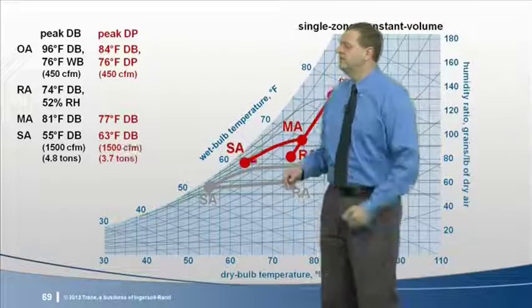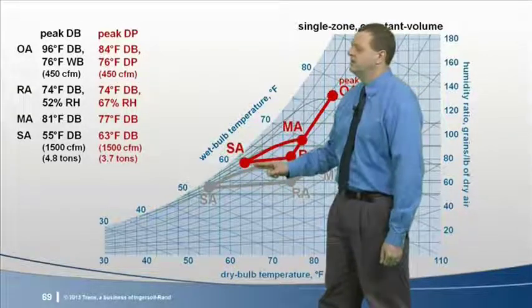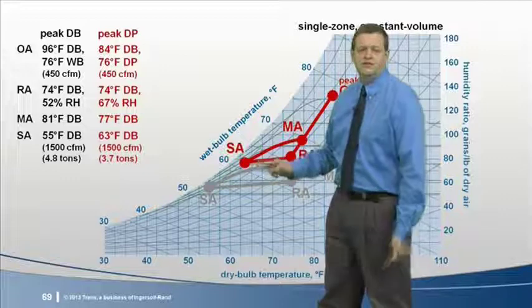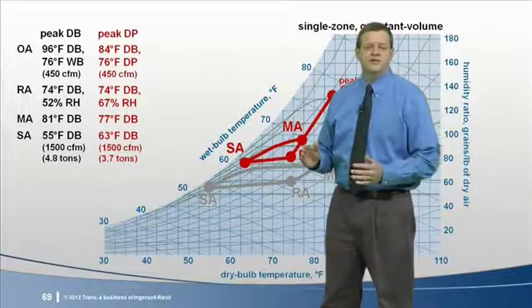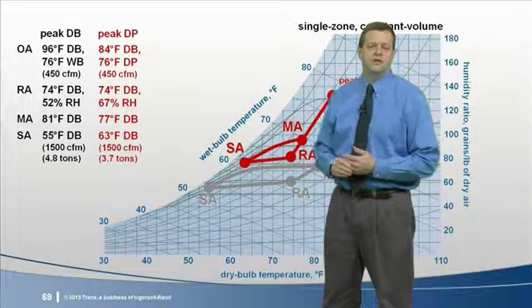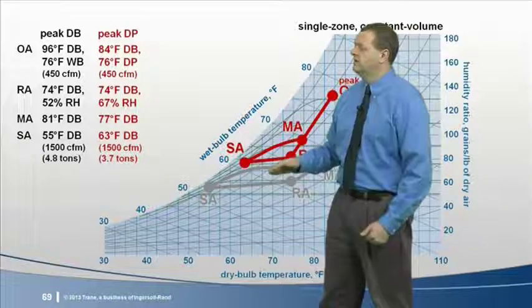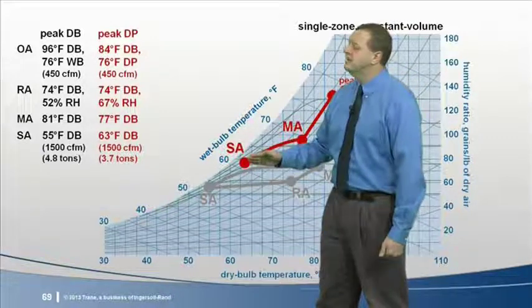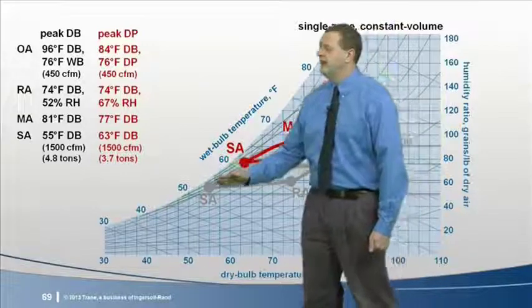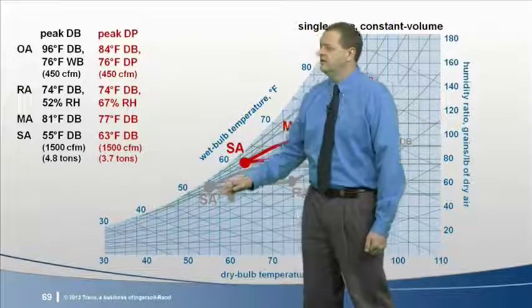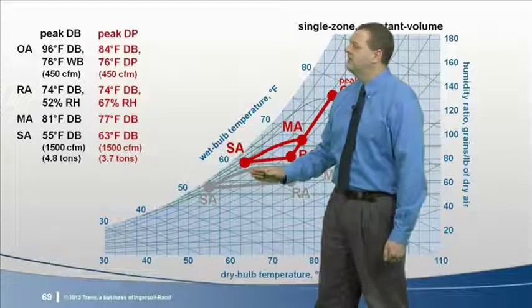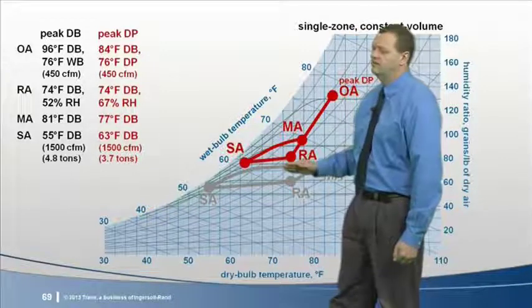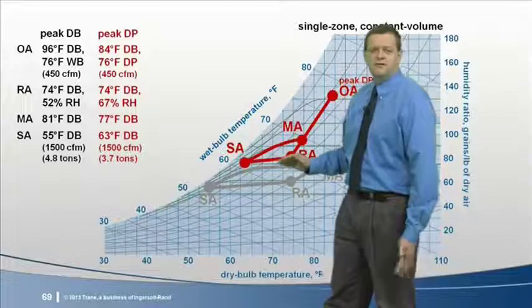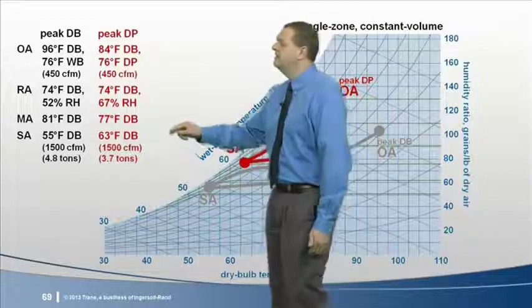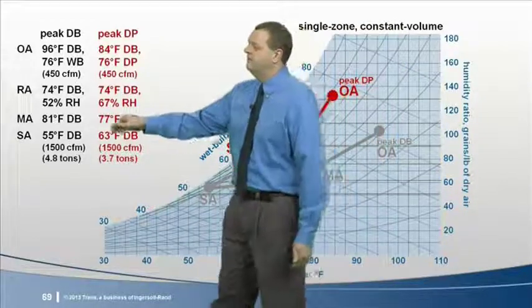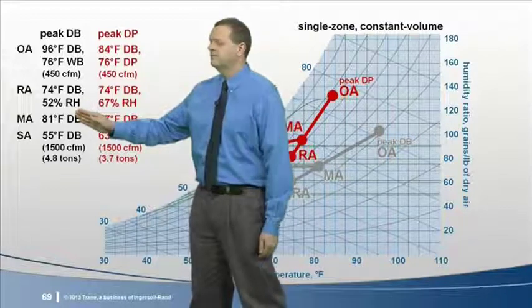Now, although delivering this warmer air prevents overcooling and maintains the zone temperature at set point, the cycling compressor results in a warmer average coil temperature and less moisture removed. This 63-degree air has not been dehumidified as much as if it was cooled down to 55 degrees. This warmer, wetter supply air causes the zone humidity level to rise. At this part load condition, the resulting relative humidity is 67% compared to 52% at full load.